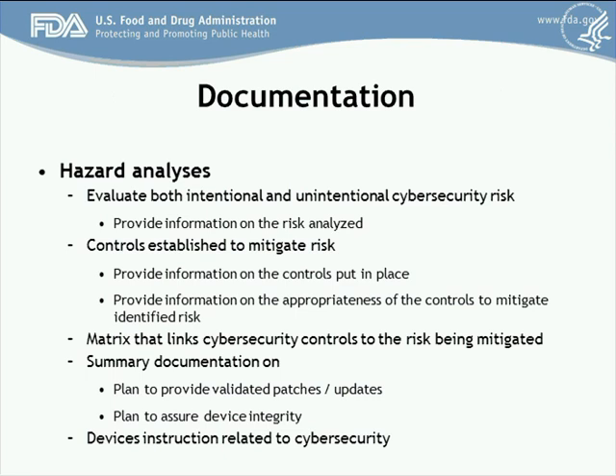The documentation that the agency would like to see in a pre-market submission includes hazard analysis, mitigation and design considerations pertaining to intentional and unintentional cybersecurity risks associated with your device, a traceability matrix that links your actual cybersecurity controls to the cybersecurity risks that were considered, a summary describing the plan for providing validated software updates and patches as needed, a summary describing controls that are in place to assure that the medical device software will maintain its integrity while it's under your control, and device instructions for use and product specifications related to recommended cybersecurity controls appropriate for the intended use environment.